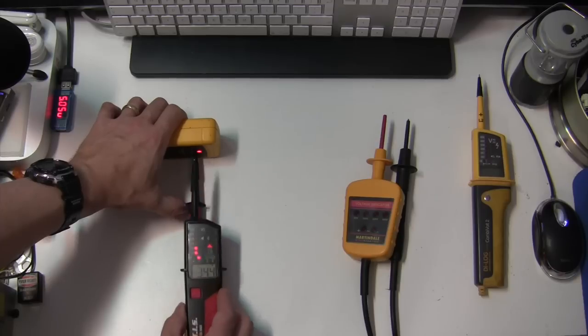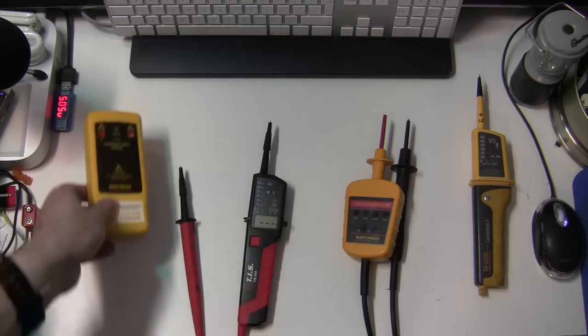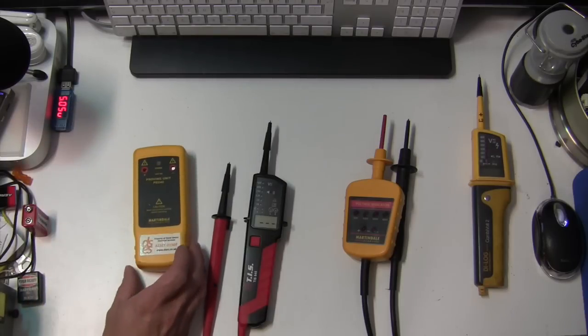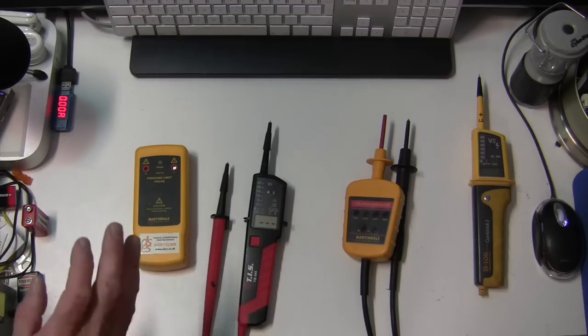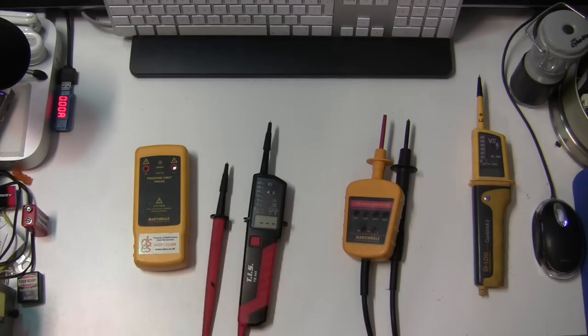So the lights light up to the 250 volt mark, and in the case of the TIS, it also gives me a visual readout on the LCD display. So the proving unit proves that my two testers are operational. So with my proving unit, we've proven that these two voltage indicators are in good working order, at least up to 250 volts. Jolly good show.